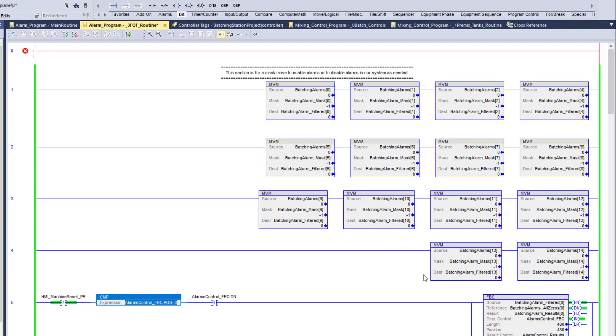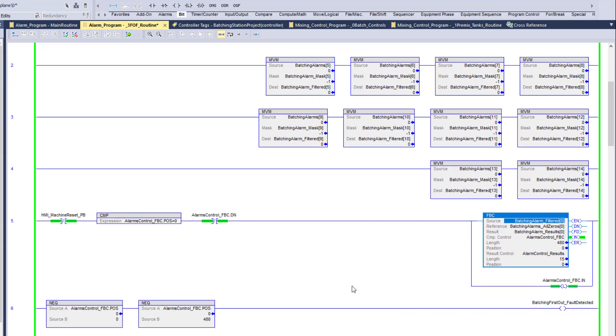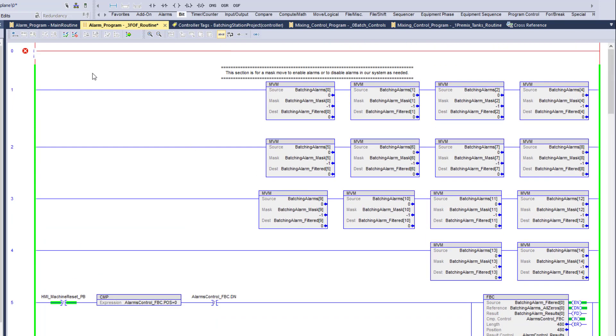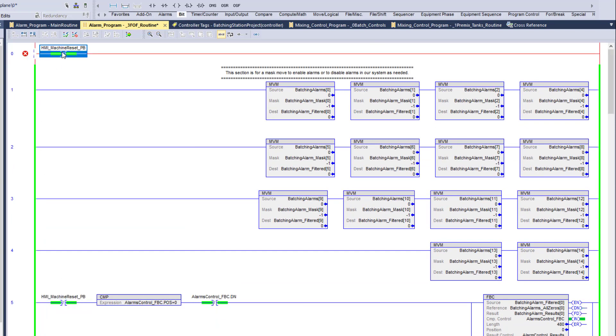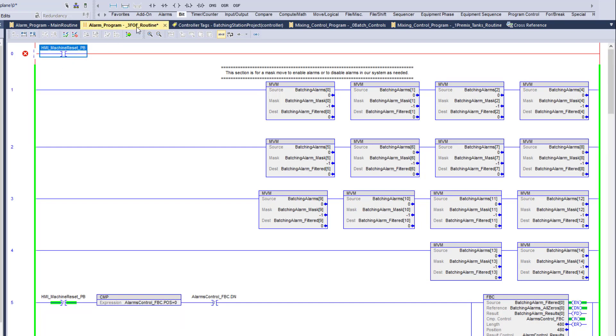This is how we're actually accumulating the first-out fault scenario. Cumulatively, it comes through and says you have a fault — this is going to be the first one detected, and it stops at that point. It's not going to continue to go. So we need to come in here and use the HMI reset and put that in.